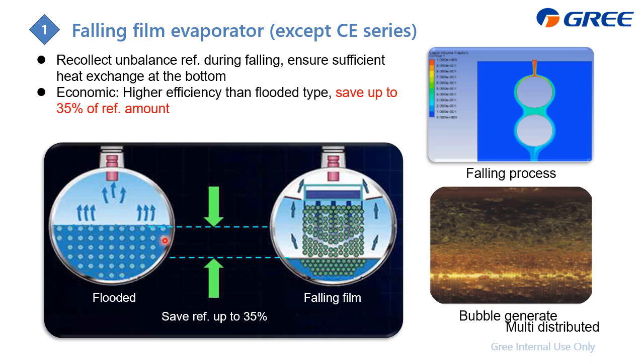And also on the other hand, for the refrigerant charge amount, compared with the flooded type, it will be definitely lower, right? And on our product, we can save up to 35% of the refrigerant. And for the flooded type, you can just consider that it's like taking a bath. And for our GREE falling film technology, it is not a bath, it's just like taking a shower, but your foot is still inside the refrigerant.